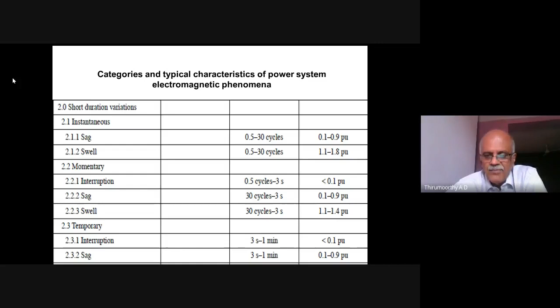Then certain issues arise in large institutions where they have large motors, and starting of large loads creates voltage sag mostly within that premises. Consequences: accelerated aging, loss of data, stability issues, then process interruption. Process interruption is a major issue in any manufacturing industry. I have not taken samples here for the presentation, but I can tell you that due to a sag of even one minute, a small sag will cause an interruption of process and production to the tune of nearly half an hour to one hour. That is a huge production loss, productivity loss and product loss also.